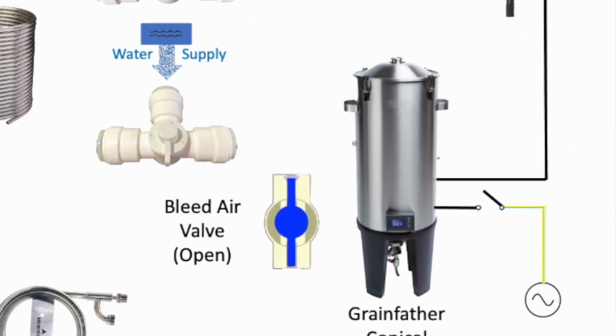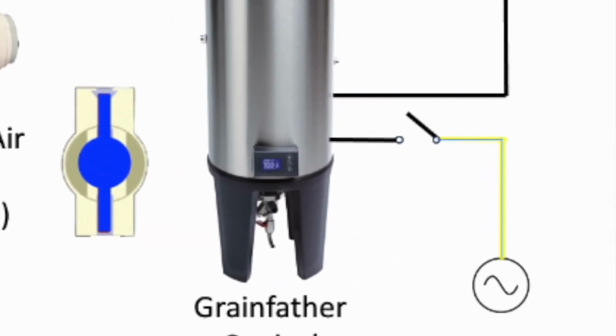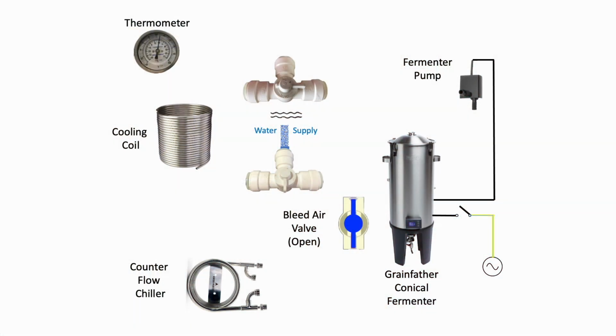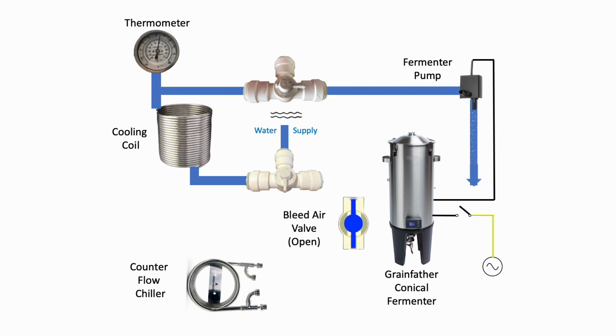With the power off to the fermenter's controller, the water circulation pump will freewheel as water passes through the pump. Water coming from the water supply goes through the valve, through the cooling coil, the other valve, the pump, and through the fermenter's internal cooling sleeve. The water is blocked from going back into the valve due to the position of the selector knob, and instead passes through the open bleed air valve into the counterflow chiller and then out the drain.